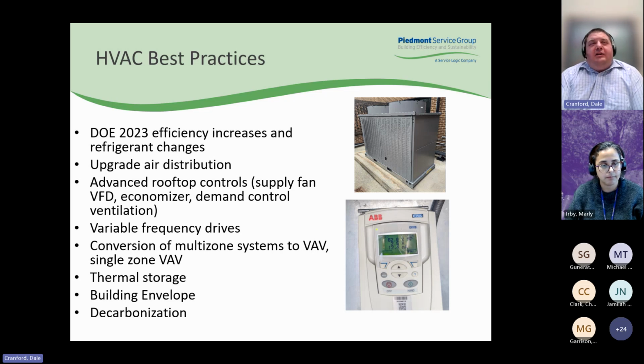Another HVAC best practice is using thermal storage, so you can make ice at night and then use that during the day for cooling. Usually the best application of that is based on your utility rate. So if you have a really high coincident peak demand during the day, or maybe you have an on-peak and off-peak energy rate, you can take advantage of a lower energy rate after hours.